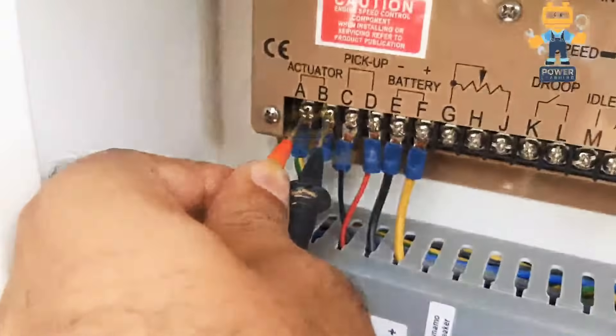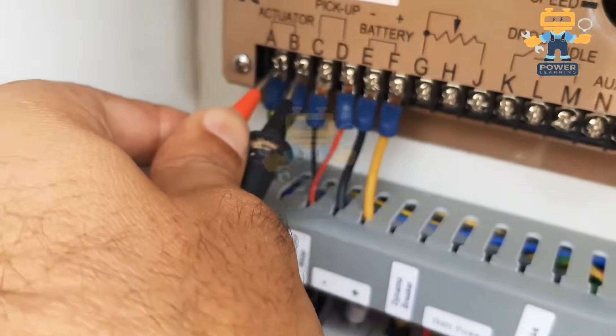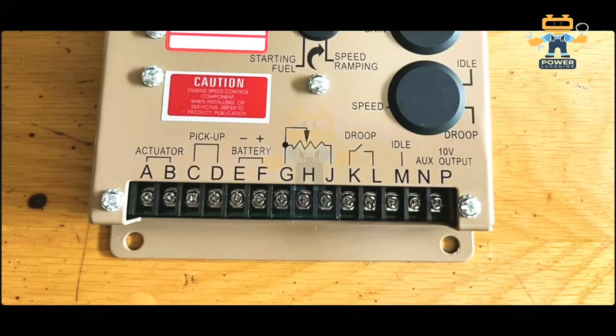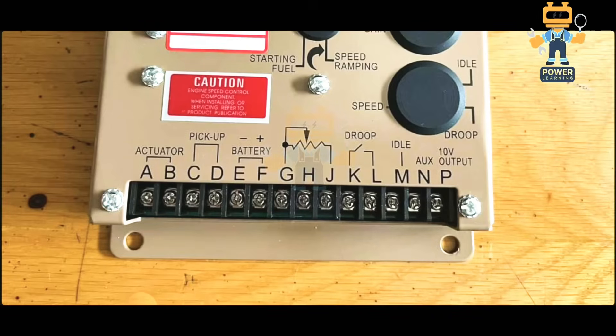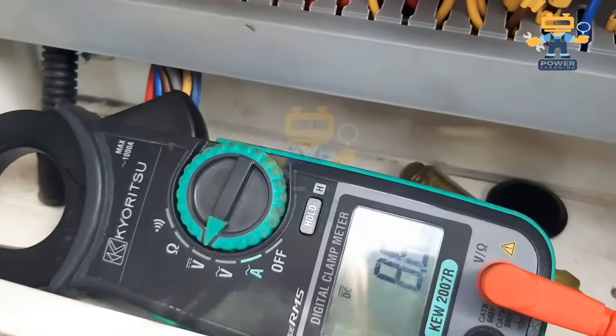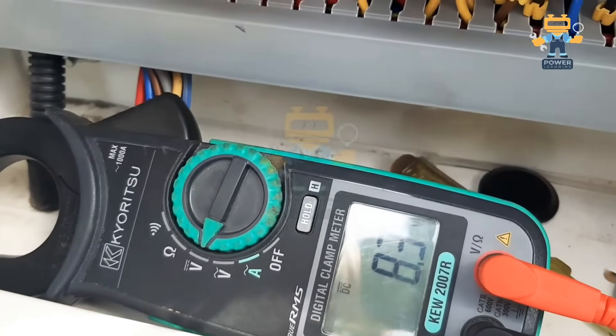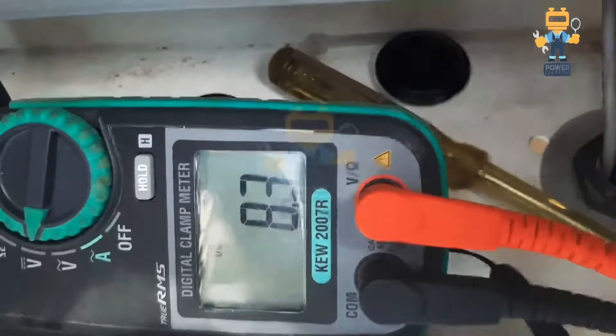The actuator is installed on our fuel pump, so we connect these two wires to the fuel pump to control the engine. The pickup signal - AC pickup signal - this controller converts this AC signal into DC and gives it to the actuator. Then this DC signal controls the engine actuator voltage. Once this voltage is decreased, the engine speed is decreased. If the voltage is increased, the actuator increases more fuel and the engine speed is increasing.